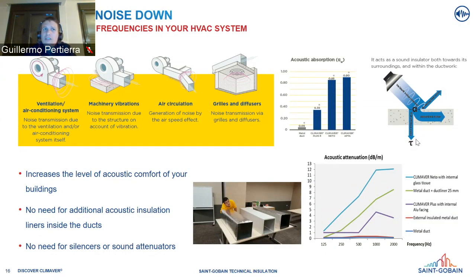Also, as you know, these silencers used to have very big pressure losses. With CLIMAVER, probably you don't need to use these silencers, and with this you save the pressure losses that the silencer costs the installation. In some cases it's also very good because you save the space needed for these silencers. So there are quite good reasons to choose this solution over others, because day by day the acoustic issue is more and more important.